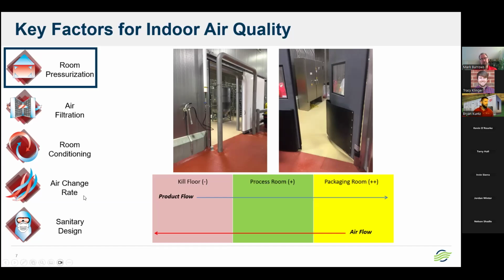So ideally, let me pull up my laser here. The product flow will typically go from the kill floor to your process room to your packaging room and then eventually out the door, right? So inversely related, you really want your airflow. So you want to expel that air outward from your process and packaging rooms to adjacent nearby spaces that may be dirty. So you definitely don't want to have the direction going from the kill floor to your process room. So with that, the other thing we like to do is get on site because we can get a full picture of what's going on at these facilities.